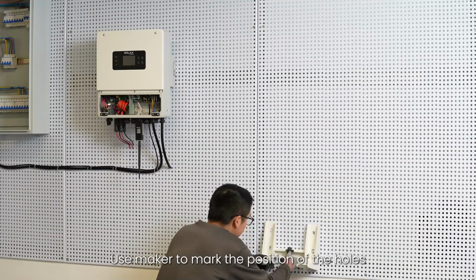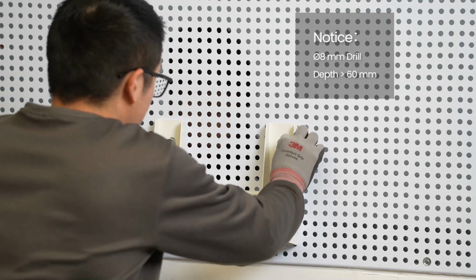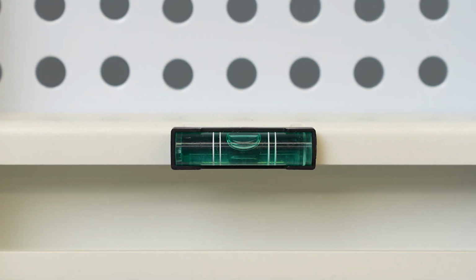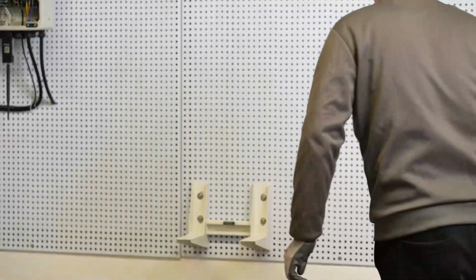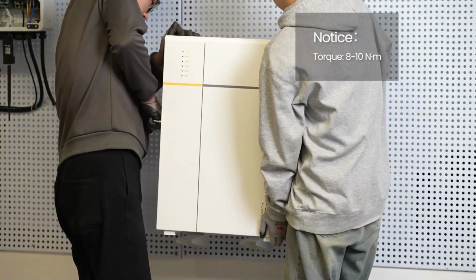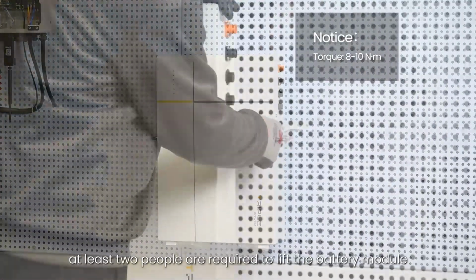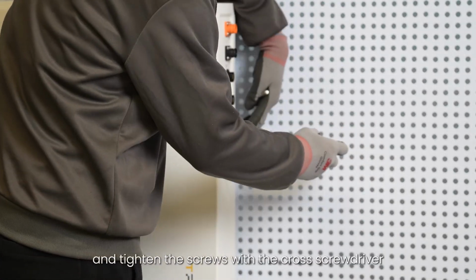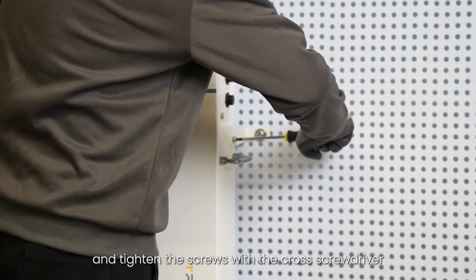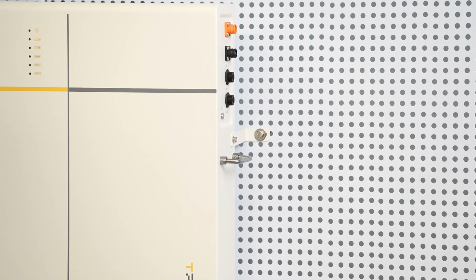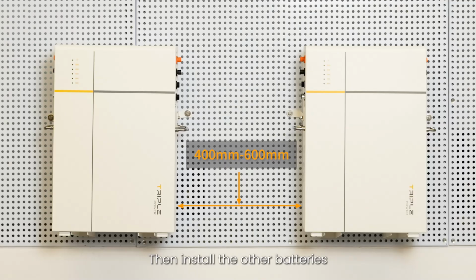Use a marker to mark the position of the holes. Note that when installing, at least two people are required to lift the battery module. Hang the battery on the wall, and tighten the screws with the cross screwdriver. Then install the other batteries. Note that 400 to 600 millimeters of distance shall be provided between two batteries.